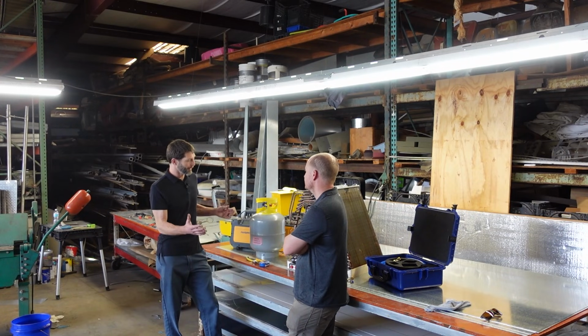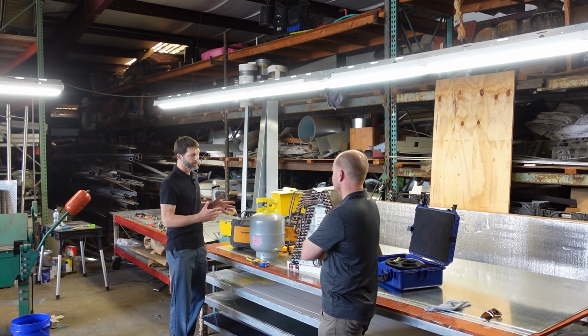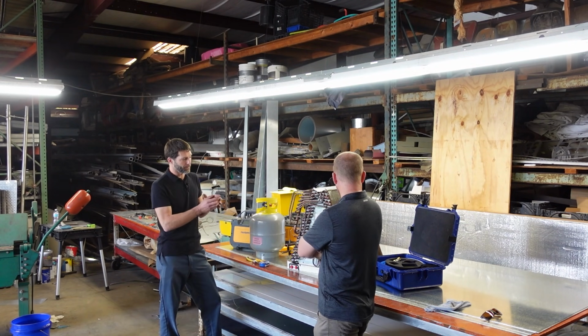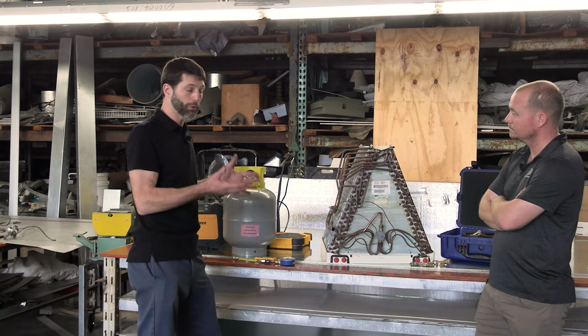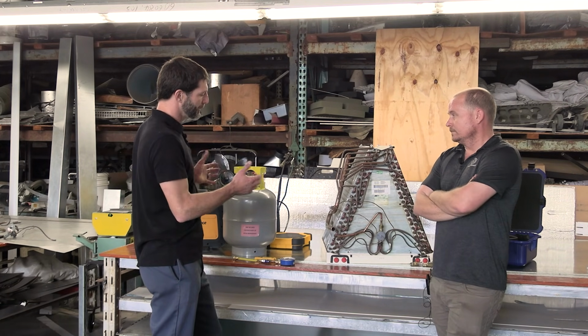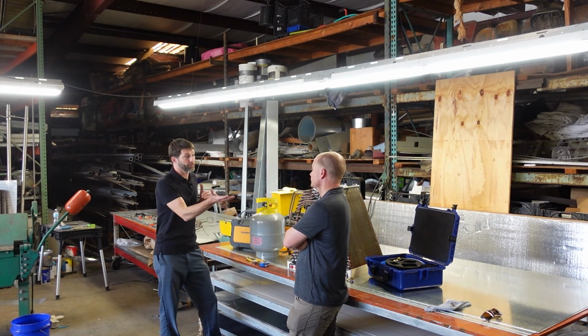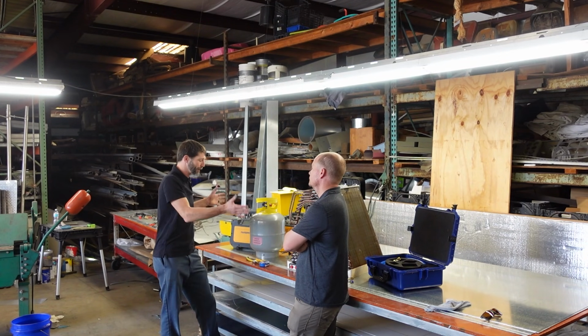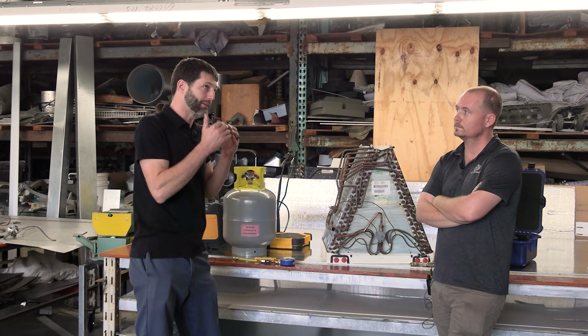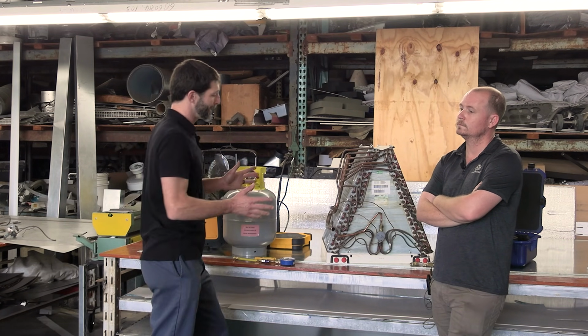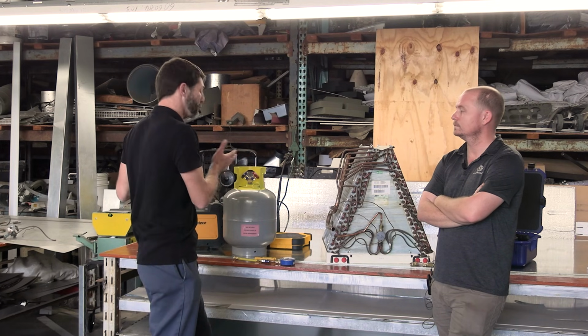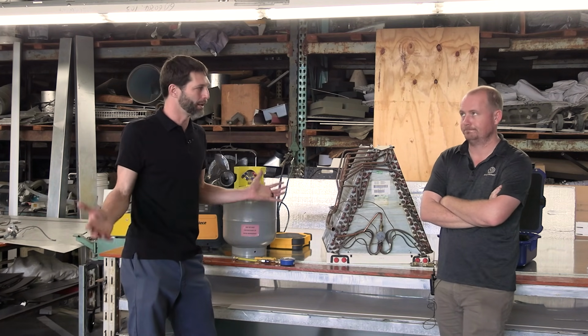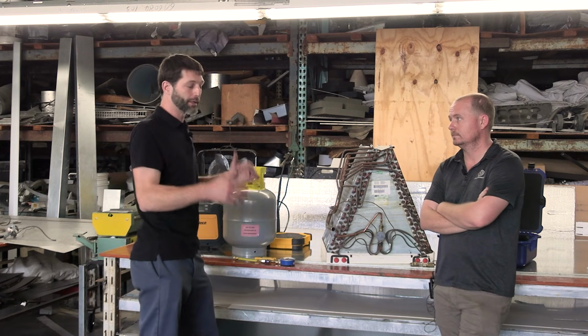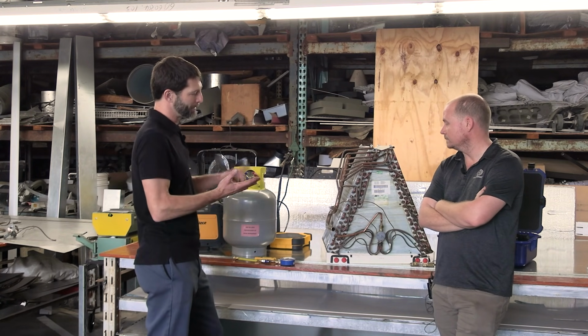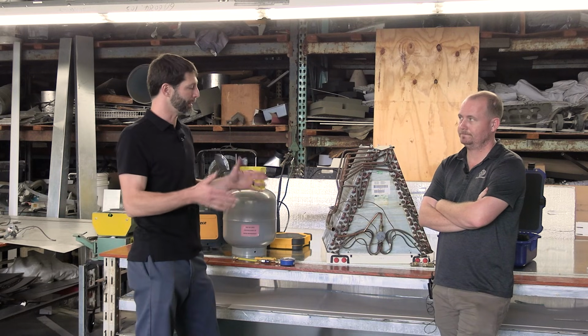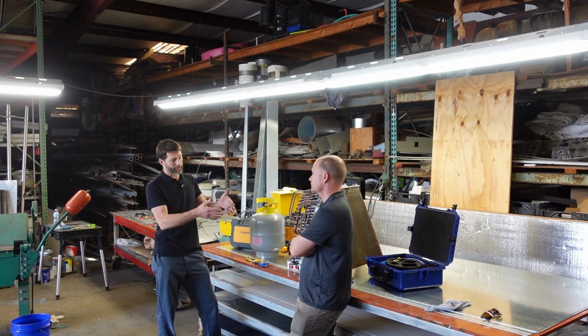Let's talk about the refrigerant hose setup. You want to have the largest recovery hoses possible, so that you get a fast recovery, and this goes to the point of heating the system up. If you have a fast recovery, it doesn't necessarily give the liquid a chance to boil off, but that's why it's important to add the heat load. But you can recover real quickly. Instead of it taking an hour, it can take 10 minutes, 5 minutes. And so you don't have to sit there for an hour and a half while leaving the valve cores in, just trying to get the refrigerant out.